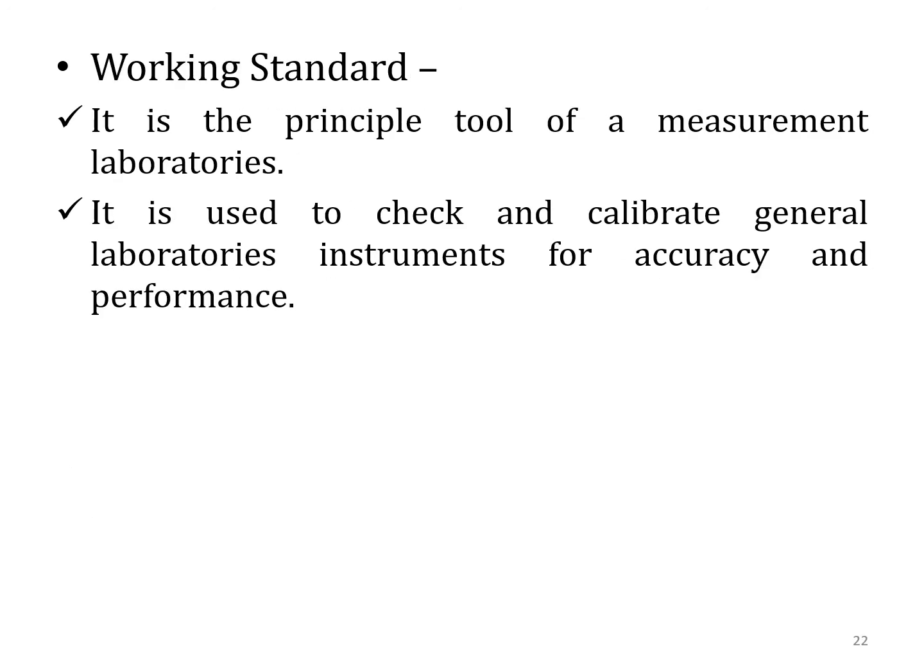Working standard. It is the principal tool of the measurement laboratory. It is used to check and calibrate general laboratory instruments for accuracy and performance.